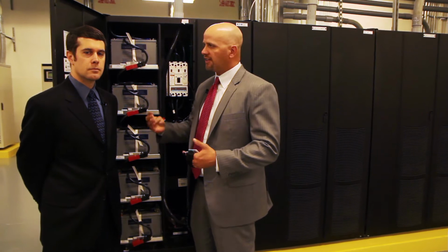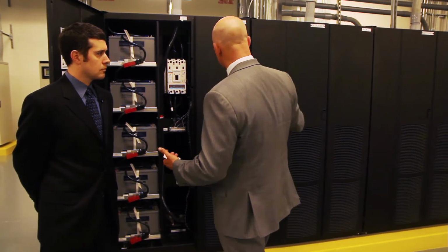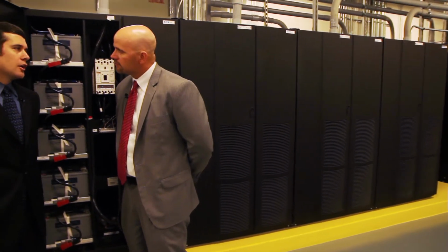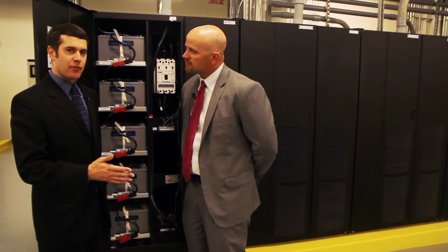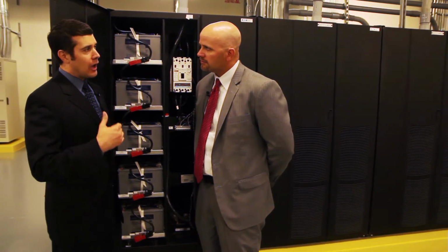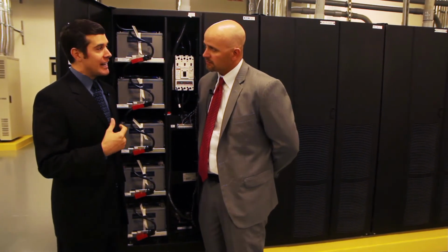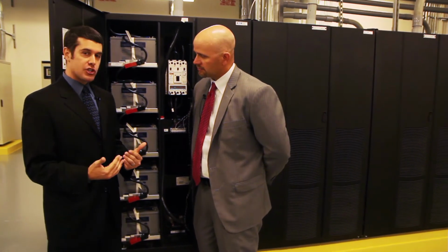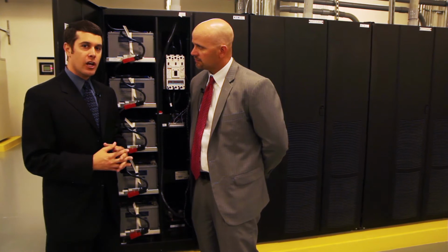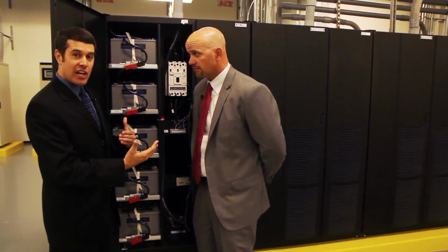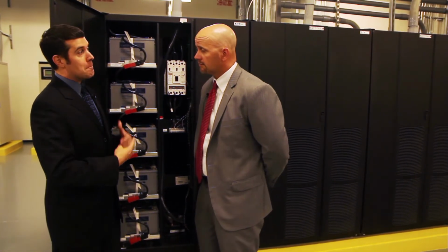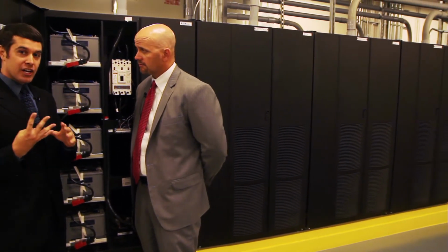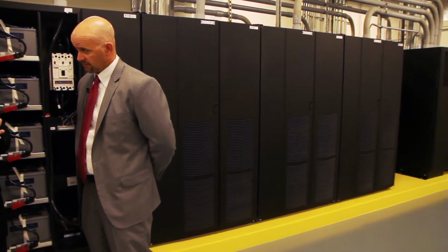But that's not the important thing, Brad. Tell us about this redundancy, N+1. Yeah, if you guys remember from last time, there was that one single UPS at the bottom of the rack, but the term concurrently maintainable, and having whatever you need +1, is a huge advantage of coming to a data center facility. So for instance, this data center actually requires 3 modules worth of these, and so it actually has 4 because there's the need +1 additional.